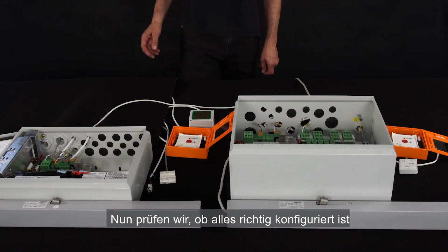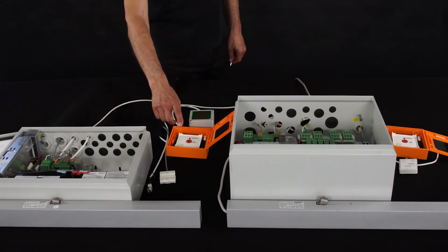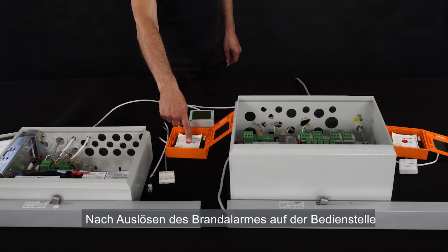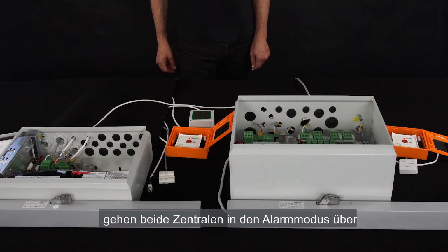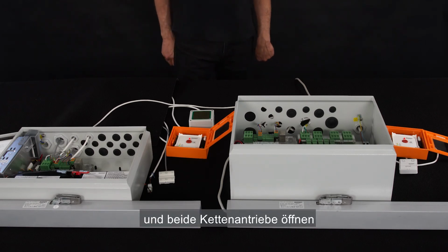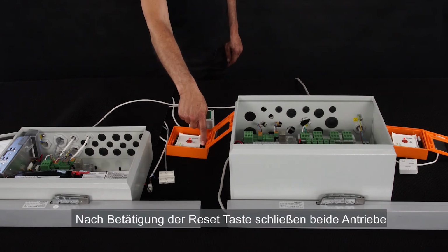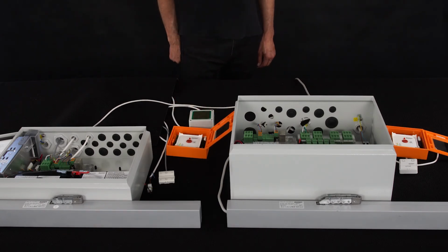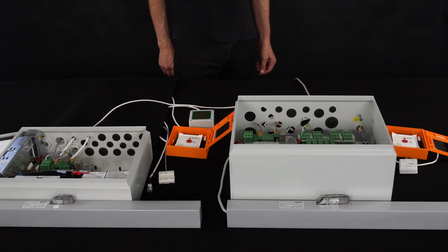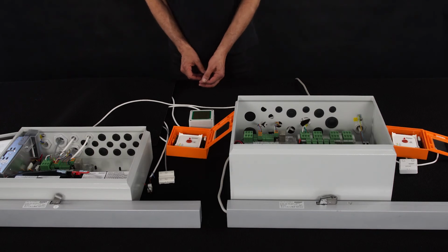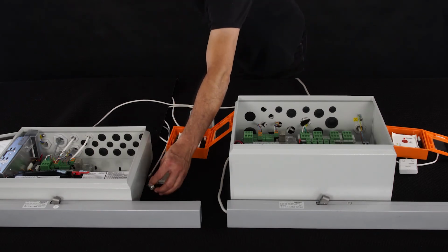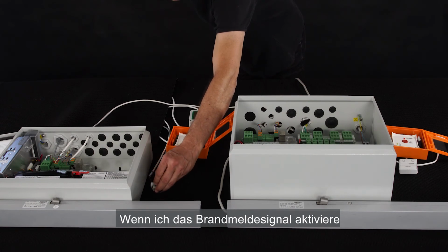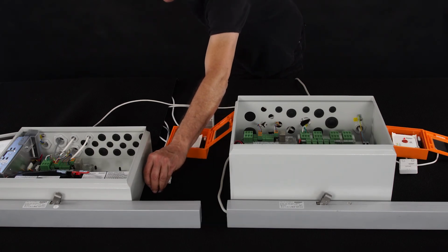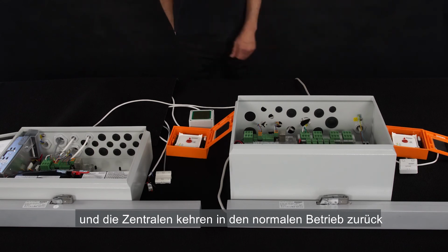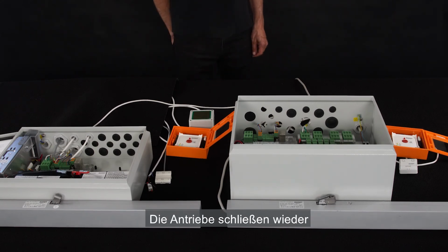Let's see if everything's working according to the configuration I've made. I activate the fire alarm from the break glass unit, both panels enter alarm mode, and both actuators open. I press the reset button and they both close. If I activate the fire alarm signal, again both actuators open. I deactivate and the panels go back to normal operation and the actuators close.